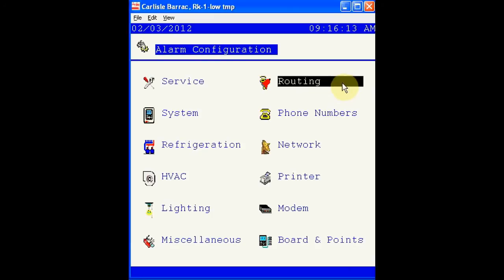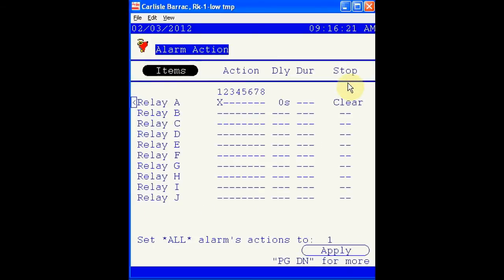Routing contains information about how the alarms are sent out from the controller and which alarms are sent from the controller. Starting at the top, you see an alarm relay is activated. These action numbers can be defined on any alarm. It's really a way to group alarms into 8 different groups, because some alarms may be routed in one way and other less important alarms may be routed a different way.